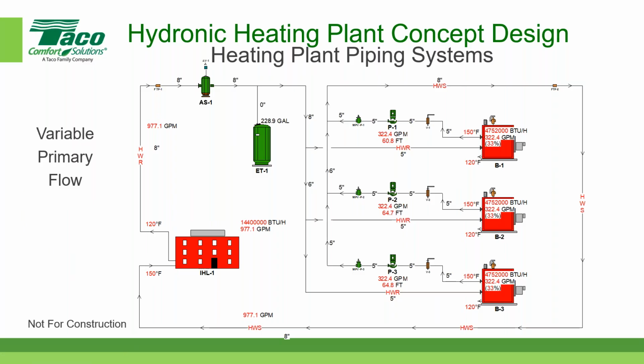But you have to do some more thinking about how your boilers are set up, the minimum flow rate required by the manufacturer, and whether or not you need a bypass and all of those other things to take into consideration. So this gives you just a quick snapshot of a variable primary flow system. Here's a great question. By the way, Syed, who asked about the 67%, patted you on the back and said, great explanation. But Jonathan is asking, do you generally pull through a boiler or push through the boiler with the variable primary flow plant? Well, it depends on so many different things.